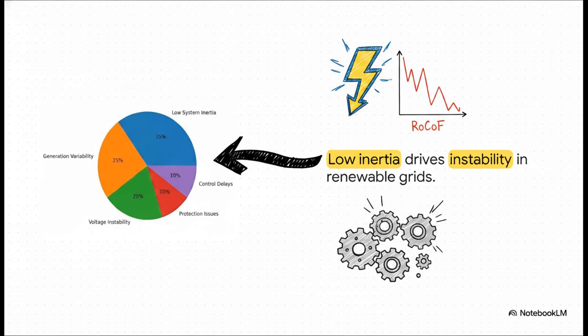This breakdown of instability sources in renewable-dominated grids is incredibly telling. Low system inertia makes up a massive 35% of the instability pie. When generation drops unexpectedly or demand suddenly spikes, a low-inertia system just can't absorb the shock. This leads to terrifyingly fast frequency deviations, often referred to as a high rate of change of frequency, or ROCOF. If that rate rises too fast, automated protection systems kick in and parts of the grid just shut down entirely to save themselves.